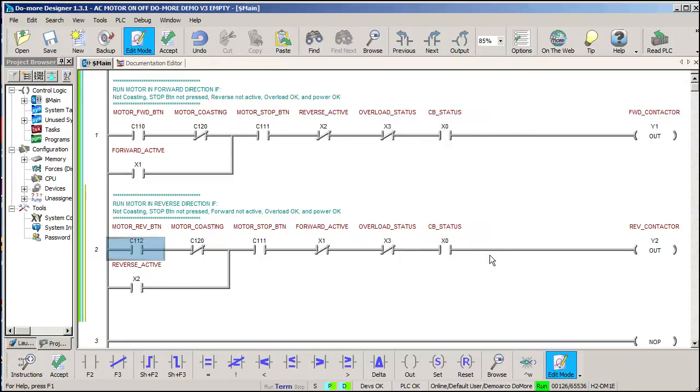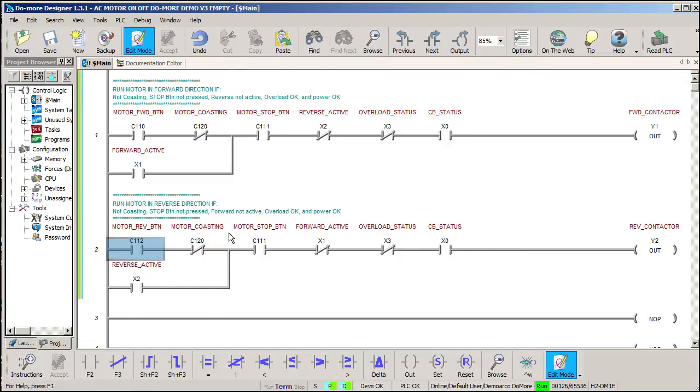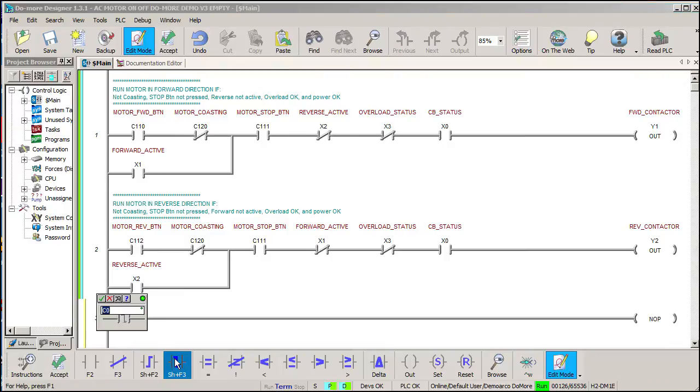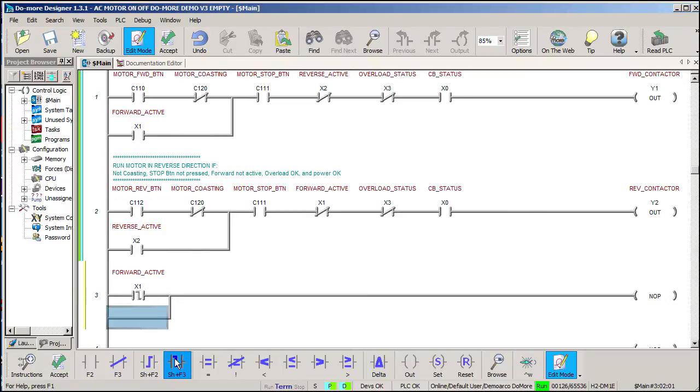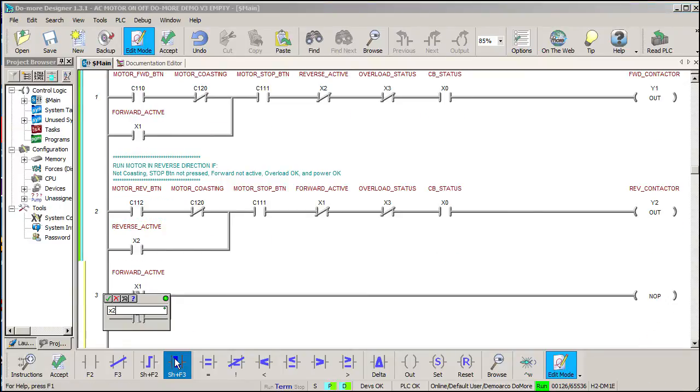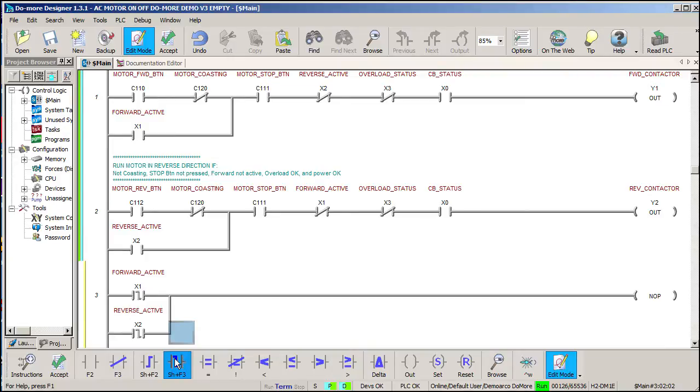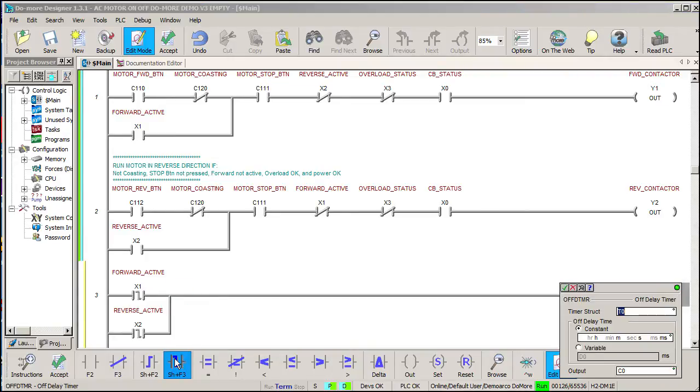We need a 5 second timer for the motor spin down, so we'll watch both contactor's AUX contacts and if either one of these gets released, we'll start an off timer. An off timer starts a timer AFTER the input has been released. During that time, we'll set a bit called motor coasting.